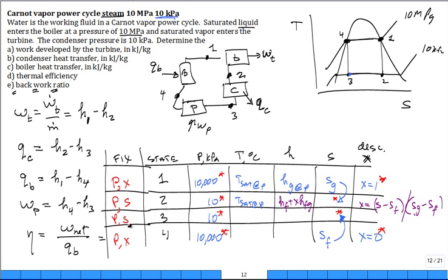Okay. All these look good. What's the temperature at the 10 kilopascal Tsat? Let's fill in this number right here. What is that value? It's around 45.8 degrees C. Hot? Cold? What do you think? Pretty hot, isn't it? So the water going through the condenser is at 45.8 degrees C. True? It's hot compared to my lake water. What's my lake water? 20-some degrees C. True? So I'm able to have a delta T, which drives the heat and condenses in the condenser. There's a heat transfer out of the steam, out of my working fluid in the condenser.